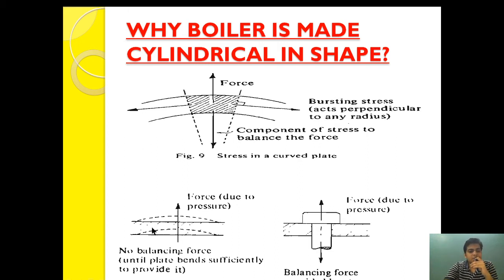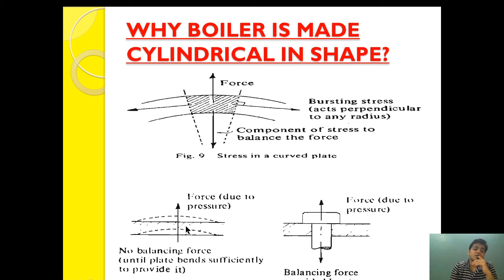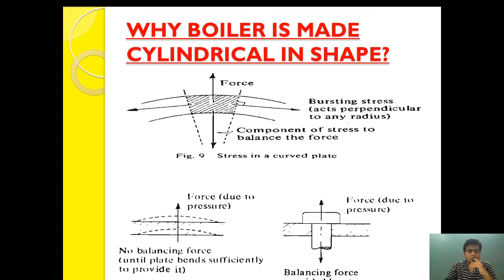But if the same force is applied to a plane surface, it will cause distortion, and the flat surface is unable to generate the balancing force. The cylindrical shape has the quality of generating a balancing force to withstand stress, which is why we prefer the boiler to be made cylindrical or semi-hemispherical. Flat surfaces are unable to generate this balancing force.